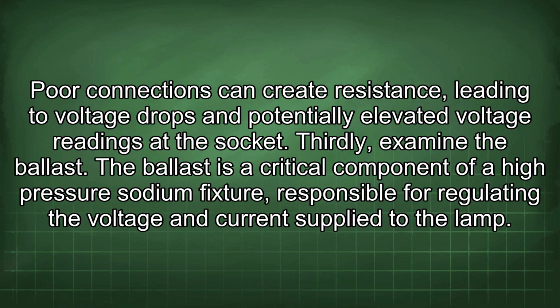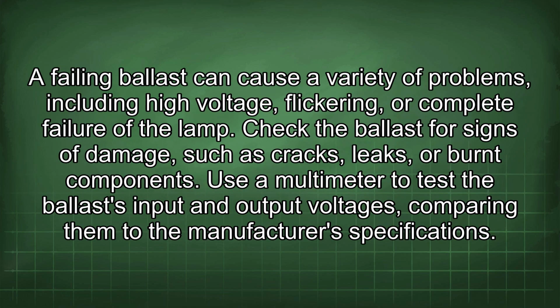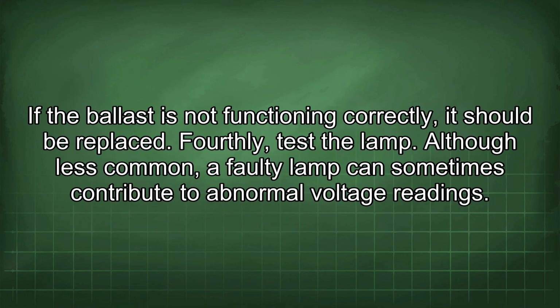Thirdly, examine the ballast. The ballast is a critical component of a high-pressure sodium fixture, responsible for regulating the voltage and current supplied to the lamp. A failing ballast can cause a variety of problems, including high voltage, flickering, or complete failure of the lamp. Check the ballast for signs of damage, such as cracks, leaks, or burnt components. Use a multimeter to test the ballast's input and output voltages, comparing them to the manufacturer's specifications. If the ballast is not functioning correctly, it should be replaced.